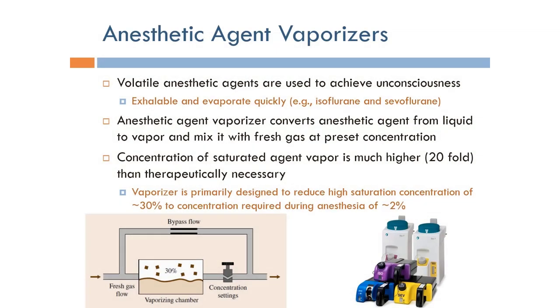The part responsible for adding the anesthetic agent is the vaporizers. Volatile anesthetic agents are used to achieve unconsciousness. We use inhalation anesthetics — agents that are exhalable and evaporate quickly, such as isoflurane. The anesthetic agent vaporizers convert the anesthetic agent from liquid to vapor and mix it with the fresh gas at preset concentrations.